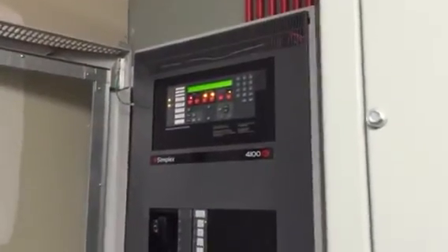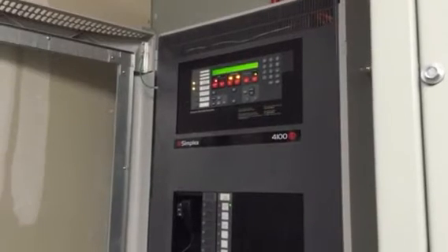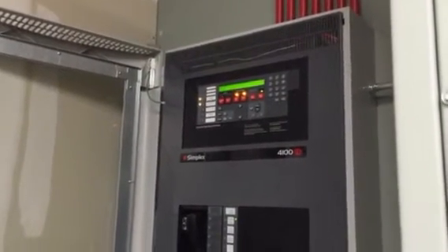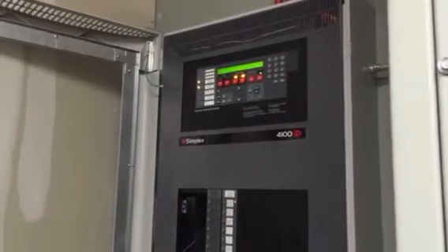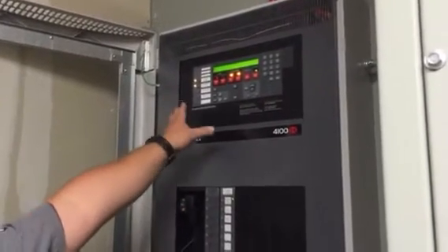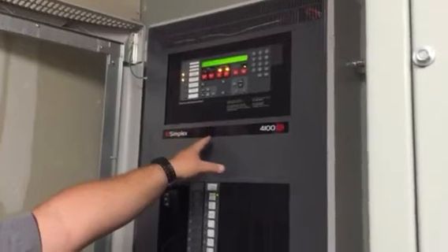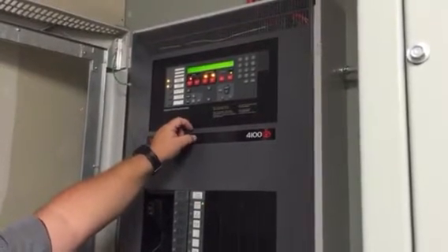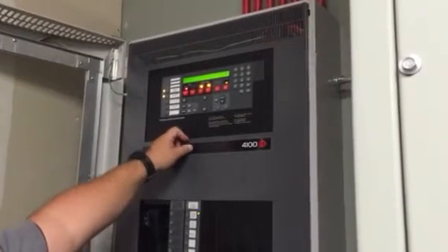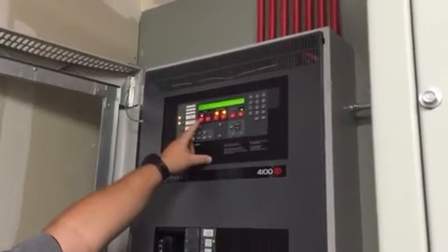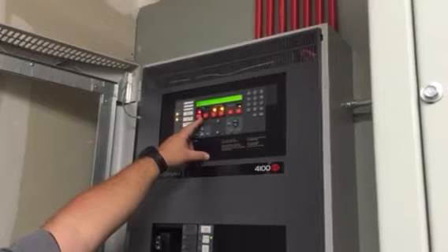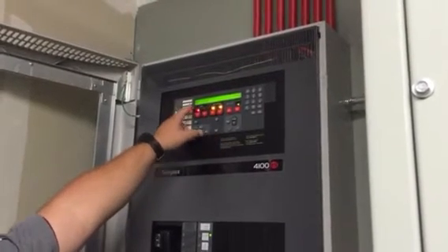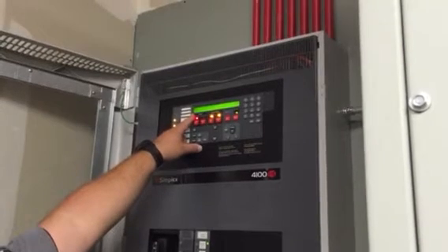Now you've got two annunciators, one by the office and then one by the other entry for the gym. So you've got those two annunciators. Right now those are beeping also. Those are giving you the same display, responding the same way as this panel is. So you can go to those, or you can come straight back here, whichever one. So you come in, you'll press fire alarm acknowledge. It'll say global acknowledge. It'll tell you the location of where the alarm went off.